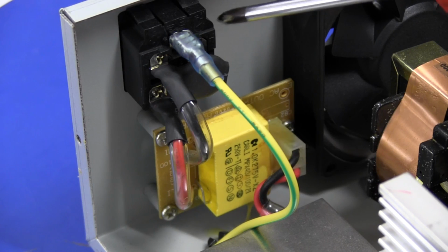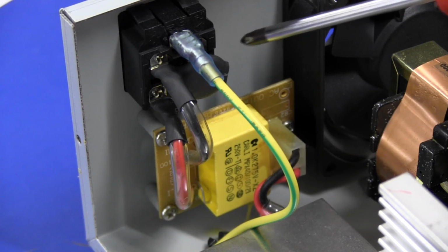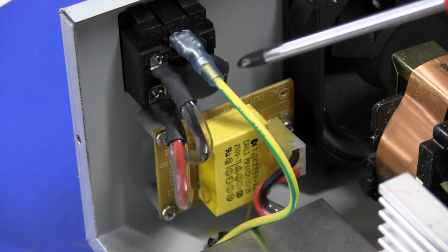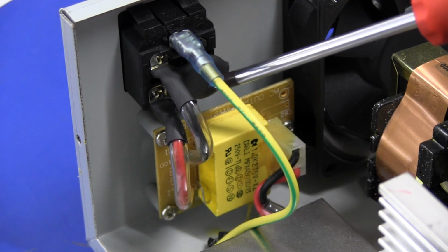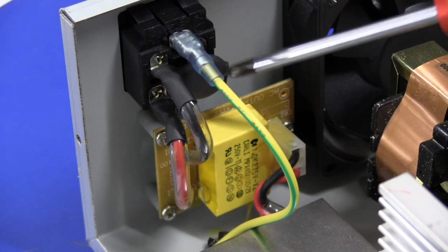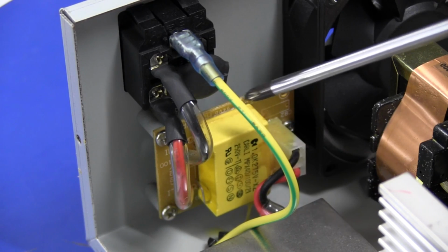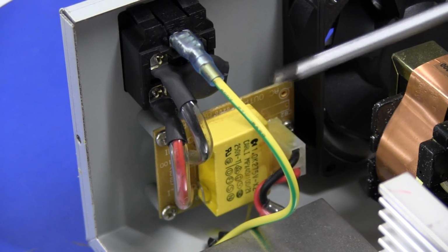Here's our IEC mains input. There's no voltage switching, it's specifically designed for 240 volts. We've got a MOV here, actually heat shrunk in a bit of heat shrink tubing - excellent, right on the terminals, exactly where it should be.